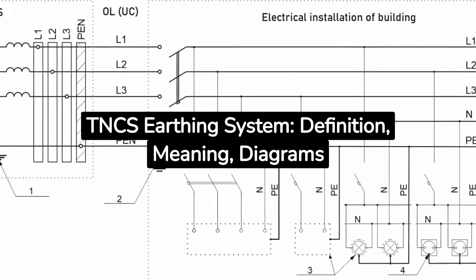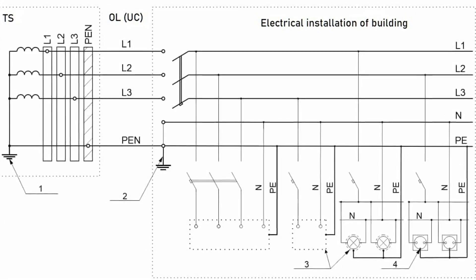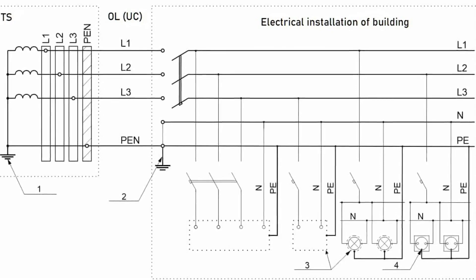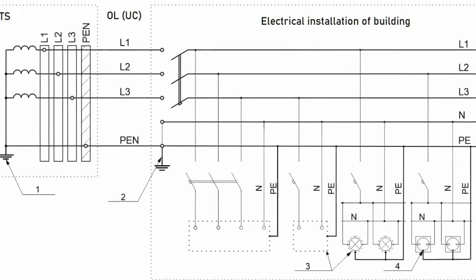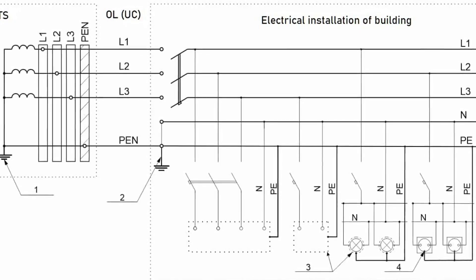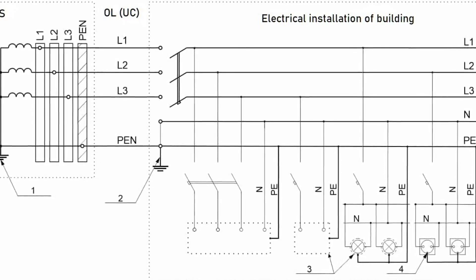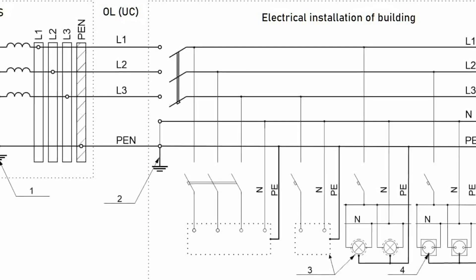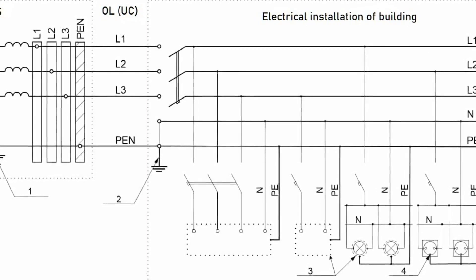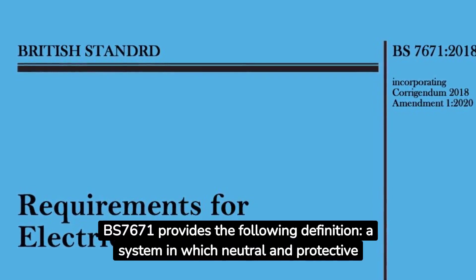TN-C-S earthing system: definition, meaning, and diagrams. The TN-C-S earthing system is a distribution system in which one live part of a power source is earthed. Exposed conductive parts of an electrical installation are connected to the earthed live part of the power source in a head part of the electrical installation by PEN, PEM or PEL conductors, and in other parts by protective earthing conductors (PE). BS 7671 defines it as: a system in which neutral and protective functions are combined in a single conductor in part of the system.